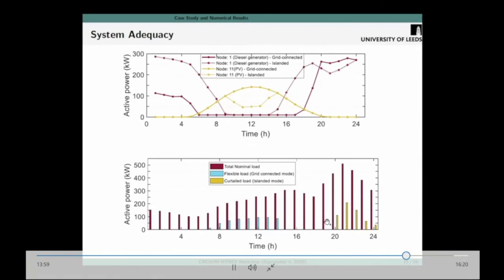We see some curtailment in islanded mode, but this is majorly during the peak hours. And notice that in this case, we have only the diesel generator providing power in the system as the PVs are off during this time. However, our critical load represented 40% of the total load at each hour, and in most cases remained served in the system.